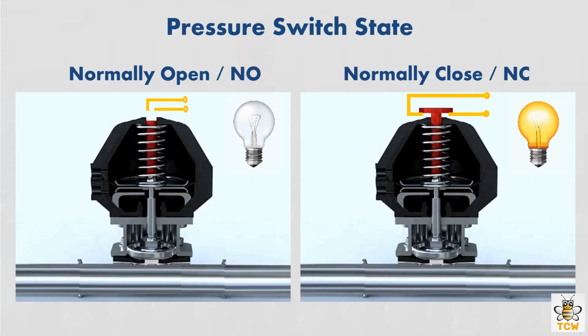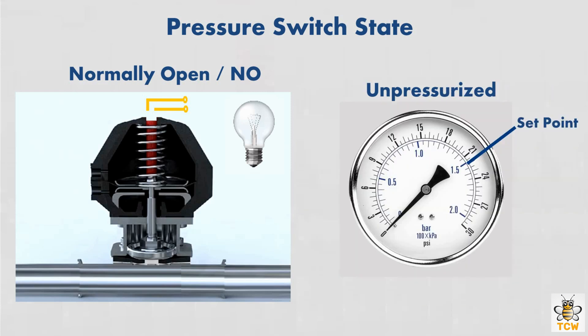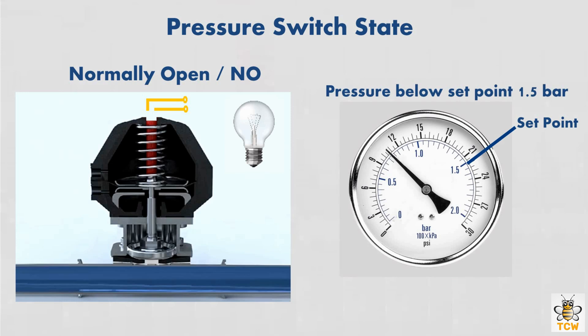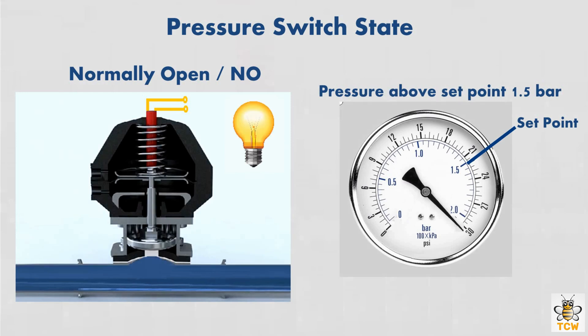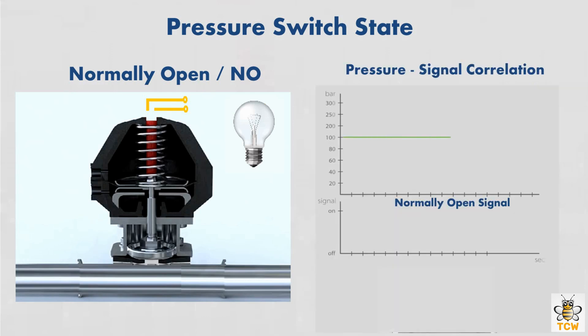Apart from the three main specifications — operating voltage, operating current, and pressure set point — the pressure switch state is another factor that needs to be determined. There are two types of pressure switch states. The first is normally open, or NO. Normally open is the state where the pressure switch is disconnected when unpressurized. It remains disconnected if given a pressure lower than the set point, and only connects when the pressure reaches or exceeds the set point of 1.5 bar.